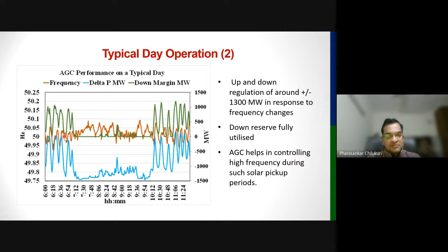During contingencies also, we have seen excellent performance during contingencies like generation loss or load loss. AGC quickly reacts by changing the load set point of the generators under remote, and it helps in driving area control error towards zero. So from 0 to 800 within 8 minutes, so around 100 megawatt per minute ramp rate. Typically, a thermal power plant gives, like I told, 5 to 10 megawatt per minute ramp rate. But AGC has so many generators under its fold, so its ramp rate is much quicker. The power of unity, because there are 10, 15 generators at a time available for dispatch. So we get 100 to 200 megawatt per minute ramp rate.